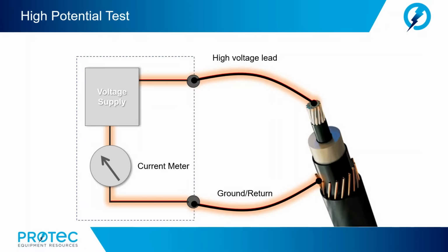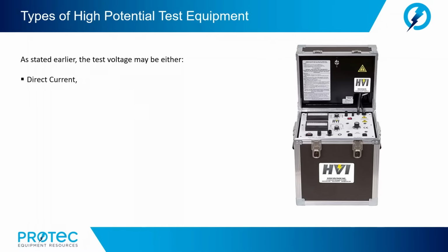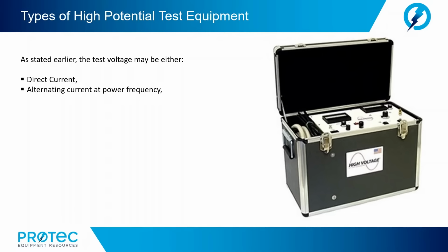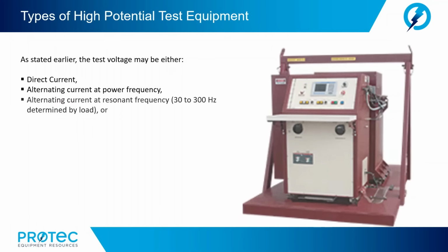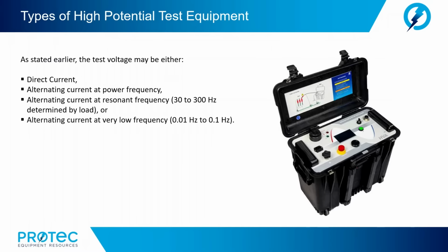The test voltage may be either direct current or alternating current at power frequency or other frequency like resonant frequency or VLF when convenient. The maximum voltage is given in the test standard for the device under test. The duration of the test is dependent on the type of test, the device under test, and various industry guidelines. Now, as stated earlier, the test voltage may be either a direct current, alternating current at power frequency, 50 or 60 hertz, alternating current at a resonant frequency, 30 to 300 hertz, again, is going to be dependent upon the load that the test set is connected to, or alternating current at very low frequency, typically 0.01 hertz out to 0.1 hertz.